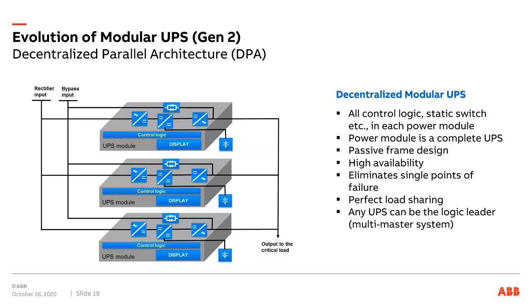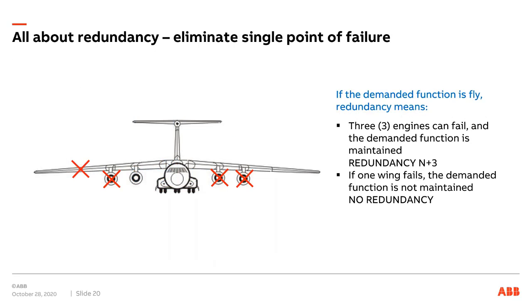So the fix to that was exactly the same as before, only now in a modular design. This is a very similar single line or one line, but this is the evolution of modular UPS to what I refer to as generation 2, which is again a decentralized parallel architecture, a decentralized design. It's just paralleling complete UPSs in a frame in a modular UPS, instead of having the control logic and the display and the static switch as shared components, fixed mounted in the frame. So the most modern, the latest generation modular UPS, this is the design we see out there. And of course, what it's all about, and this is just for a practical example, it's about eliminating single points of failure. And I'm not 100% sure.